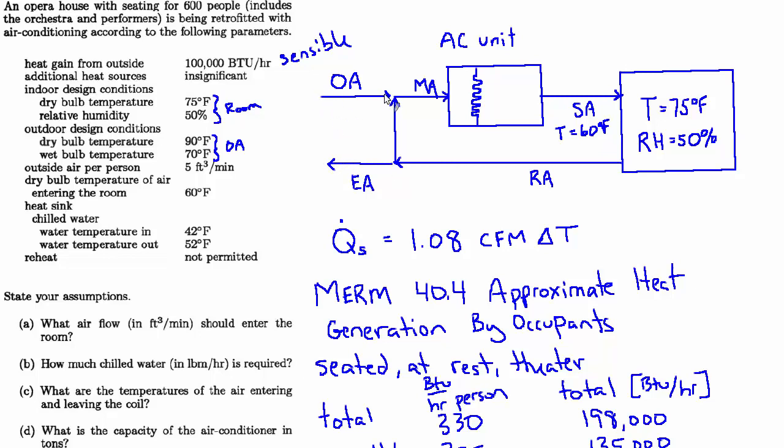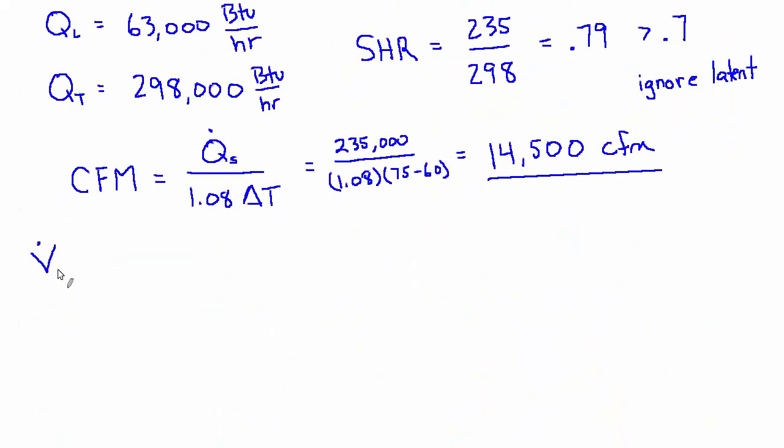Well, the same amount as whatever outside air is being introduced. Well, how much outside air is being introduced? 5 CFM per person, and there's 600 people. So the volume of outside air is 5 CFM per person times 600 people. So that's 3,000 CFM.